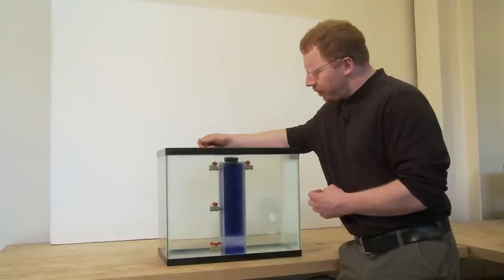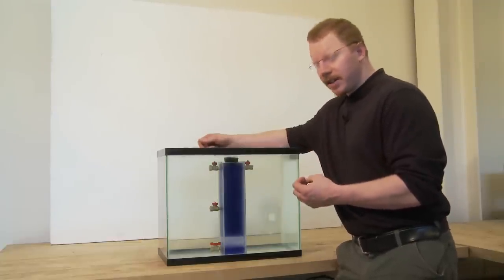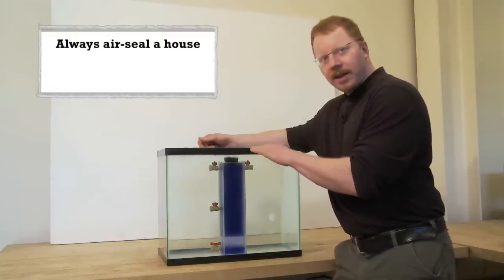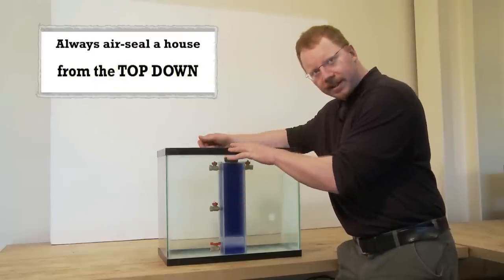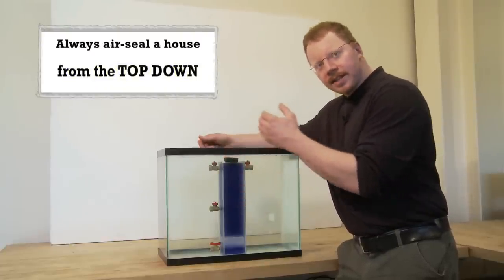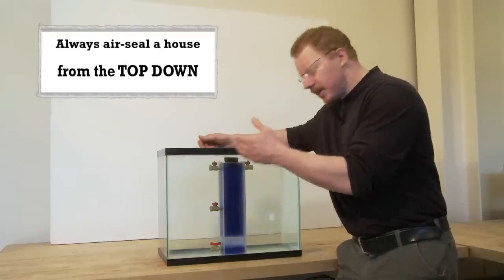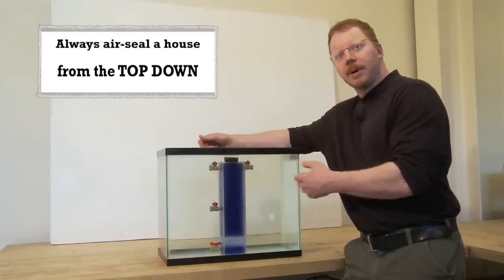This is a very important point. In order to most safely air seal a house, it's always better to air seal from the top down. If you close the holes off at the top, you will reduce that incentive to cause backdrafting of appliances and to have air leakage come in from the bottom.